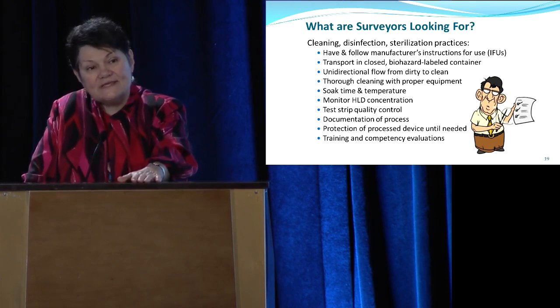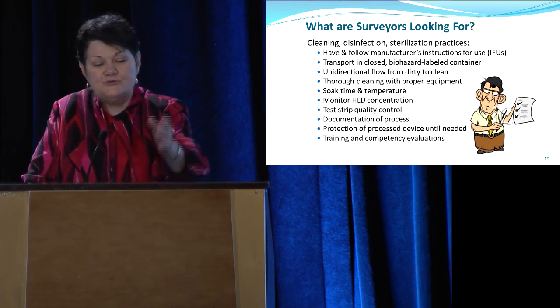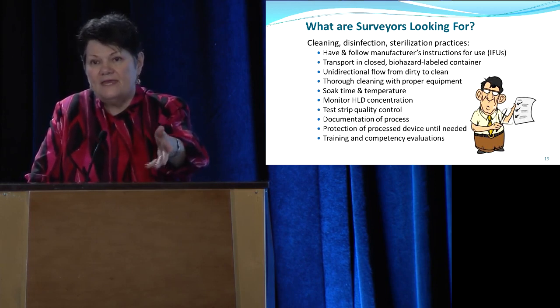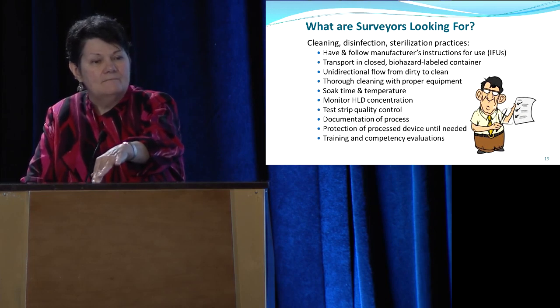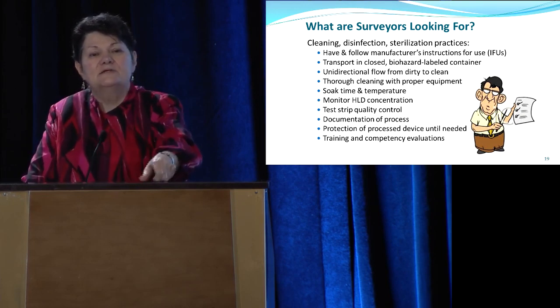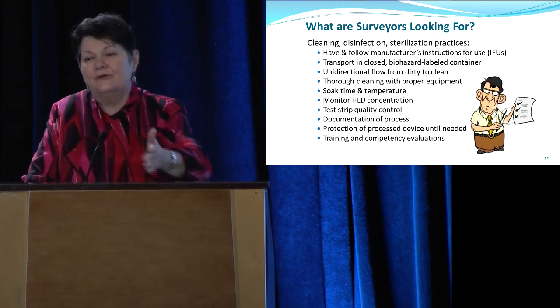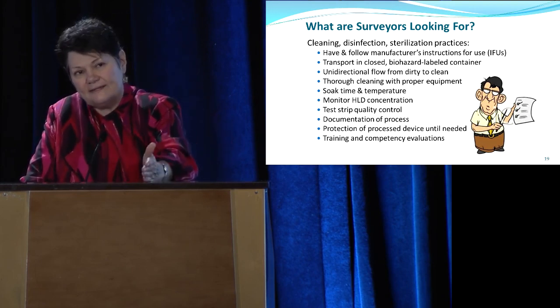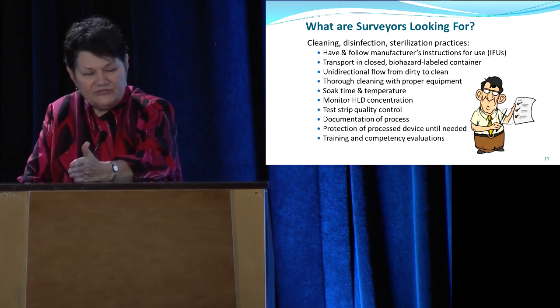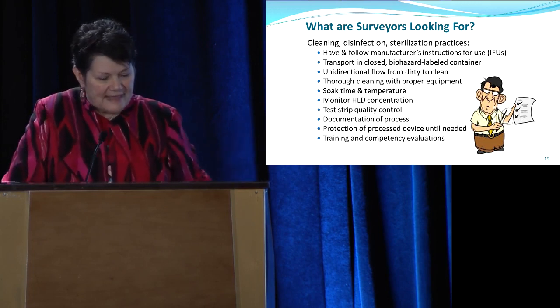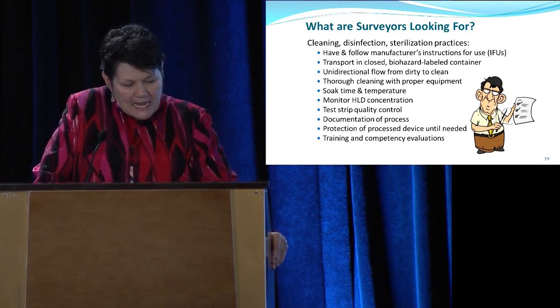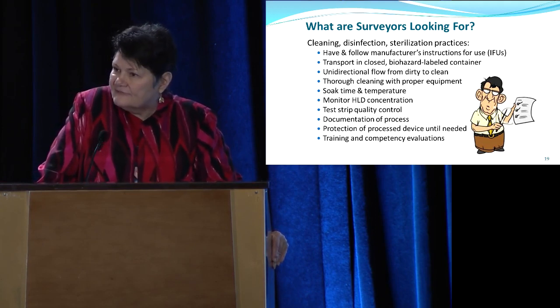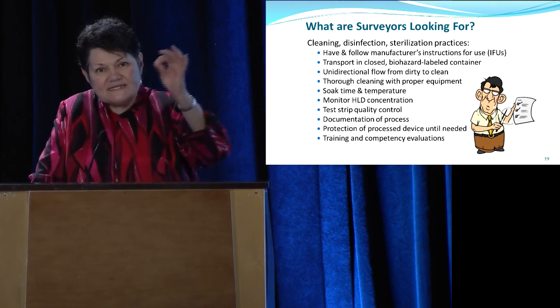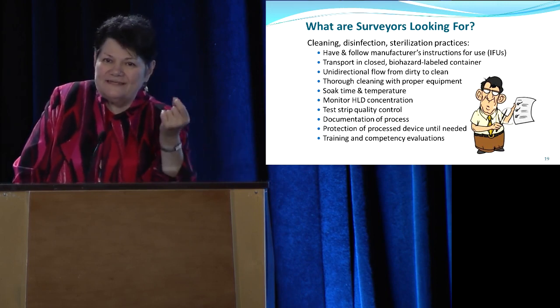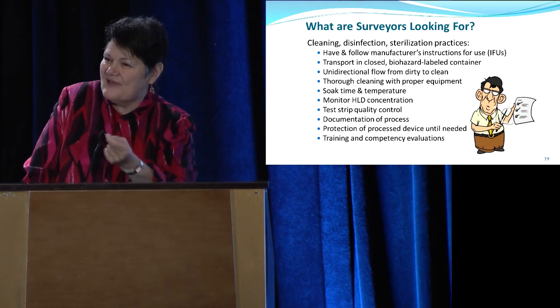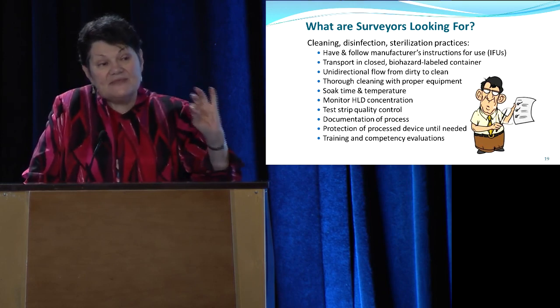And the timer gets set when the last item goes in. You can't put one thing in and time it and then add a second or third item and still take the first thing out 12 minutes later. It has to be the last item goes in, the timer is set, and it's left undisturbed until that full time has elapsed, whatever the manufacturer says. You need to monitor the high-level disinfectant concentration. There are dipsticks to do that, and you have to quality control the dipsticks according to the manufacturer's instructions. That is something I see.